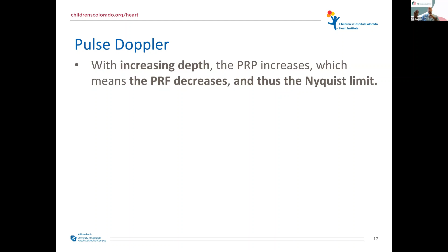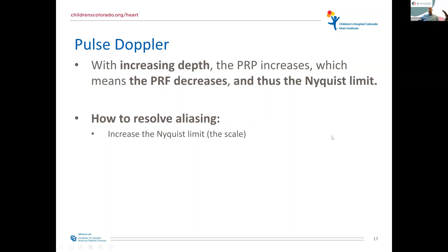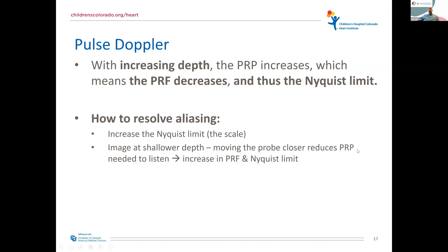So what does this mean in application? If you are imaging something and you're aliasing, then it's because your Nyquist limit is too low. So how do we fix that? Well, first, try to increase your Nyquist limit. Can I increase the scale? You actually can, and a lot of times that will fix the issue, but there's only a certain amount that you can do that. The other thing you can do is get closer to the object of interest. If you move closer, you're going to shorten the PRP, and that means you can increase your PRF and therefore your Nyquist limit. So if you're trying to image something that's 10 centimeters away, but you can get somewhere that's 5 centimeters away to image the same thing, you'll actually get a higher Nyquist limit. You're going to grab a lower frequency transducer.